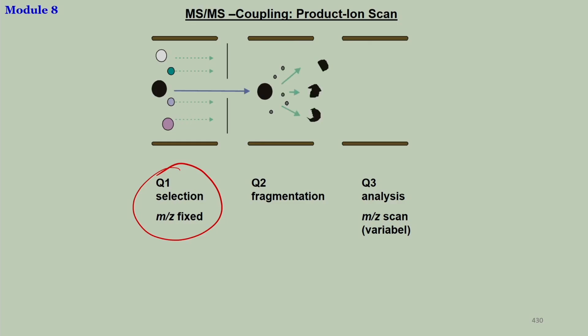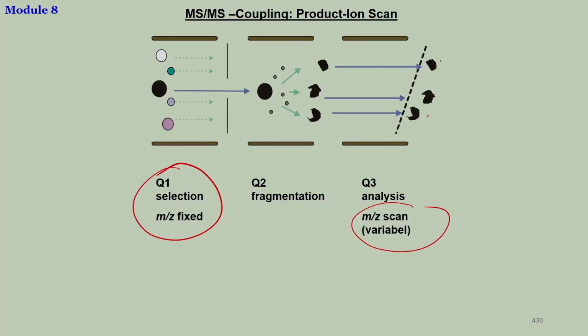This is the fragmentation pattern of this particular mass. Remember, all these masses are actually fragmented patterns from your earlier sample. So this is the next phase, the MS phase we are talking about, and from there it will analyze the fragmented patterns. That is basically it. So these are the 3 quadrupoles, and the 4th is the detector.